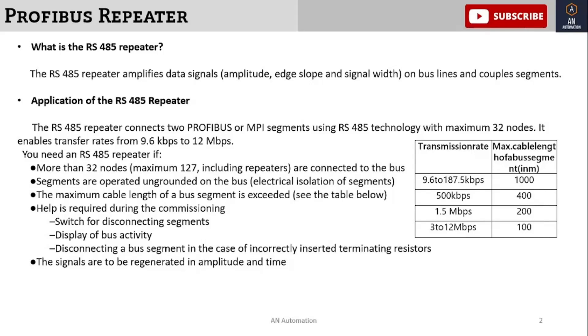You need an RS485 repeater if the network has more than 32 nodes — the maximum is 127 nodes including repeaters connected to the bus. Other use cases: when bus segments are operated on different electrical potentials requiring isolation, when the maximum cable length of the bus segment is exceeded, or when help is required during commissioning, including disconnecting a bus segment or generating amplified signals.